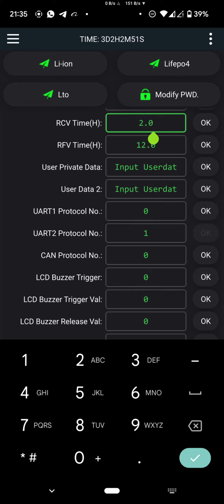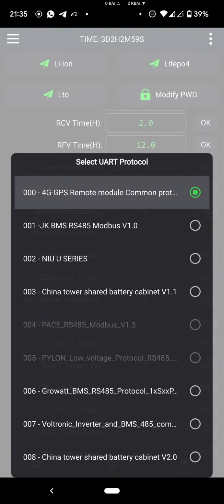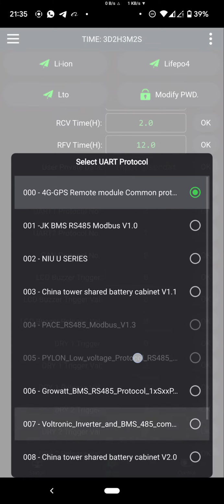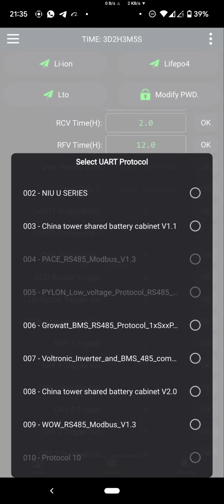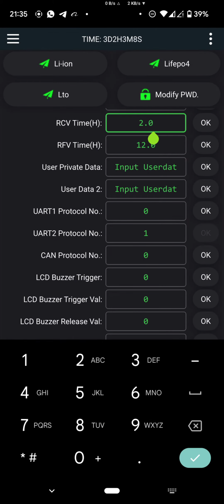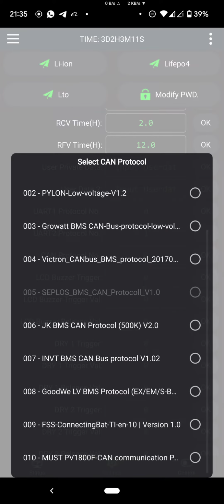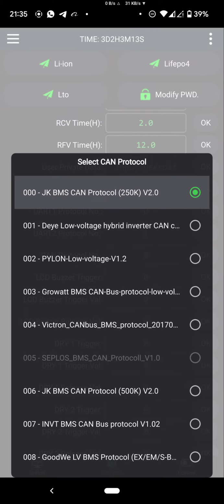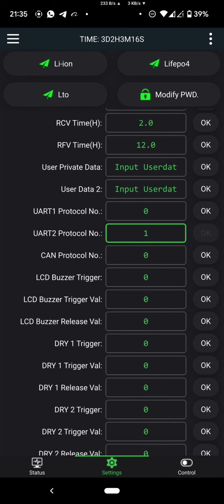Now, for communication, there are more options for both RS485 and also CAN communication. So for RS, as we can see, now we only have 3 grayed out places or options, and for CAN we only have 1. Now for this, you cannot change this. It is the value of the dip switches on the front of the communication board. So whatever you set on the dip switches is reflected in here.